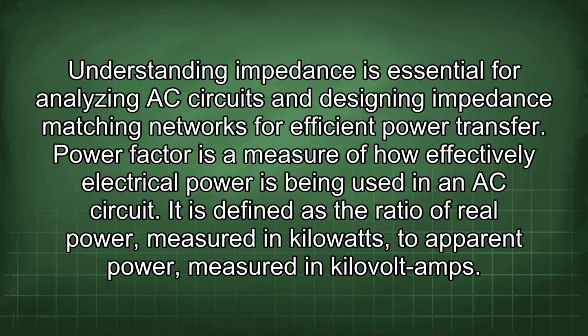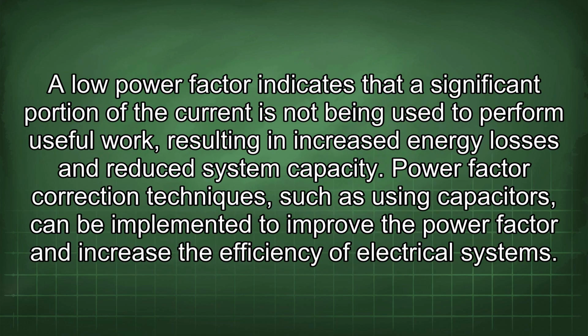Power factor is a measure of how effectively electrical power is being used in an AC circuit. It is defined as the ratio of real power, measured in kilowatts, to apparent power, measured in kilovoltamps. A low power factor indicates that a significant portion of the current is not being used to perform useful work, resulting in increased energy losses and reduced system capacity.